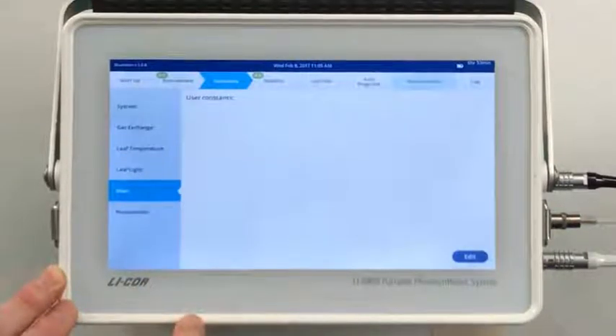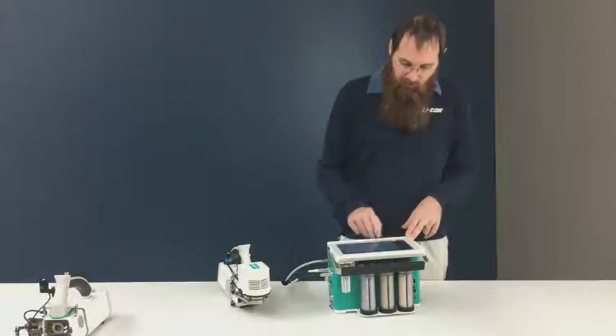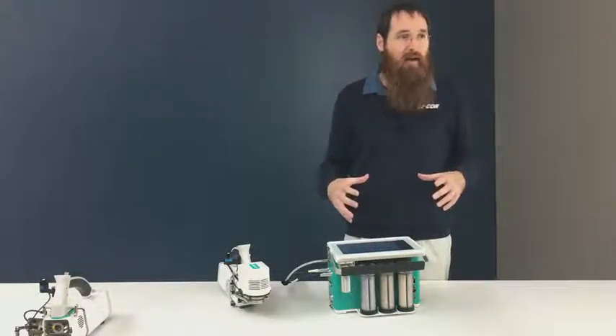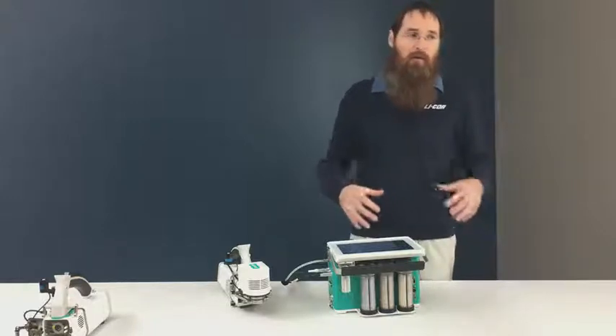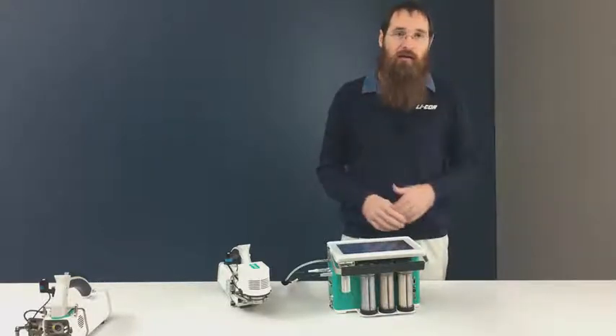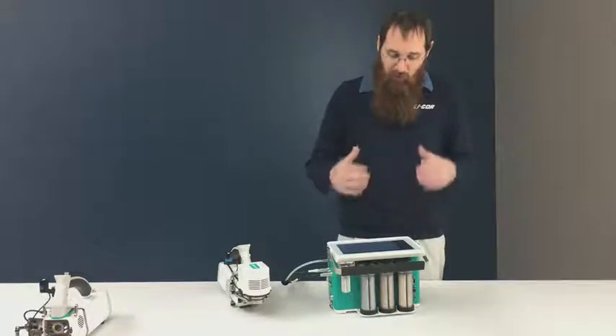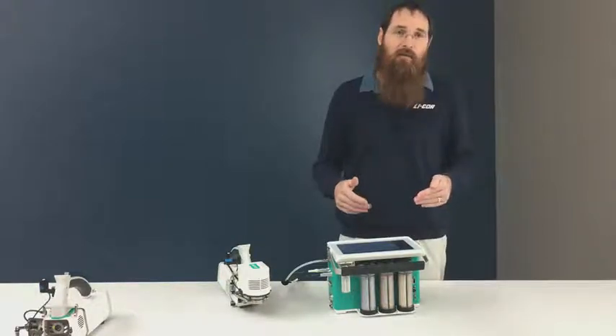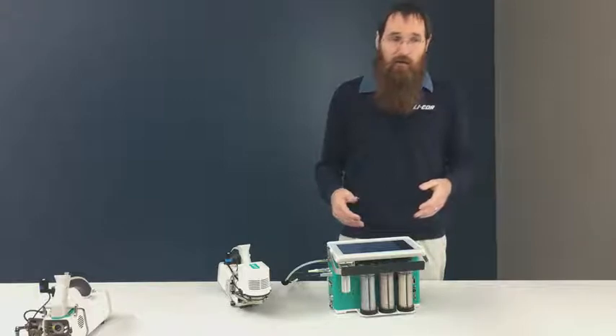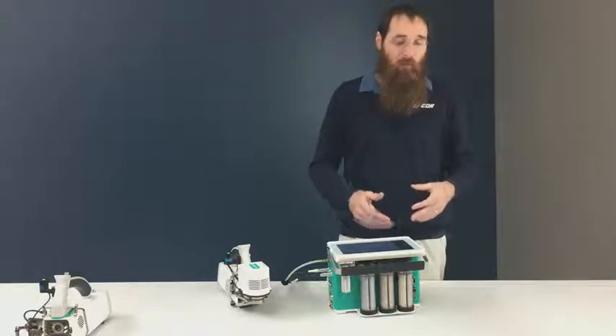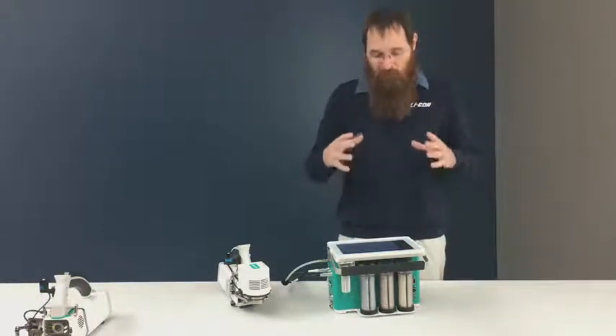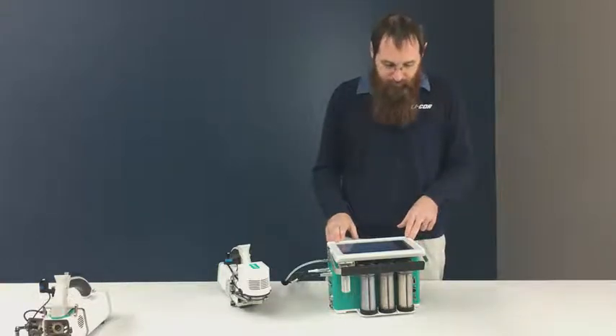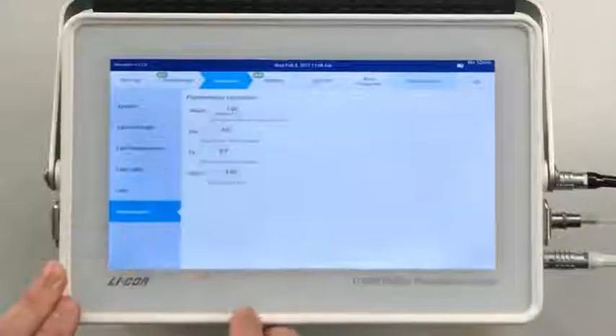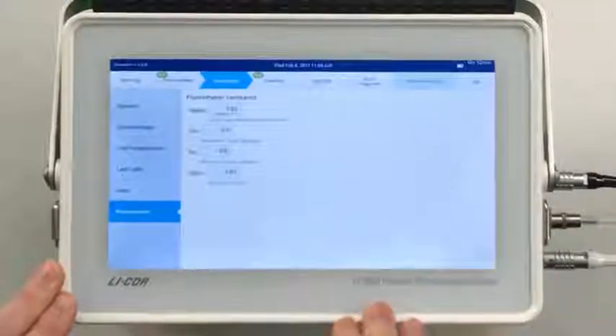User constants, this is something that we would have called prompts in previous instruments. This is where I can create a user-defined variable, something like plot number, species, replicate. I can create these variables, and then when I log data, the instrument will give me the option to input answers to them, and it will associate that data with the appropriate measurements in the final file that the instrument generates. Okay? Fluorometer has constants for the fluorometer.